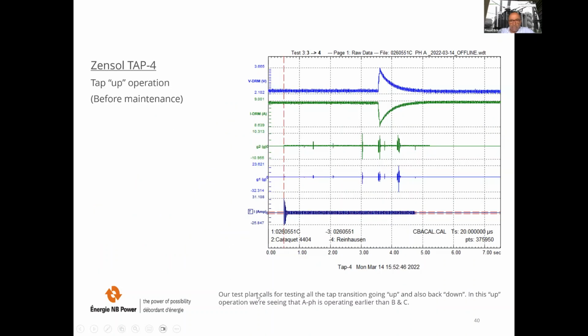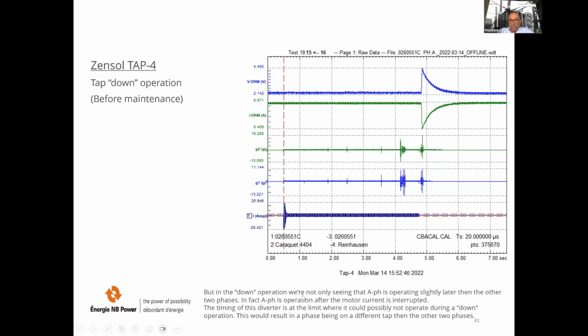So before maintenance, our test plan calls for testing all the tap transitions going up and also back down. In this up operation, we're seeing the A phase is operating earlier than B and C, as you can see here. But in the down operation, we are not only seeing that A phase is operating slightly later than the other two phases. In fact, A phase is operating after the motor current is interrupted. This is what you can see here. The motor current ends here, and the transition is happening after the motor current. So the timing of this diverter is at the limit where it could possibly not operate during a down operation. This would result in a phase being on a different tap than the other two phases.